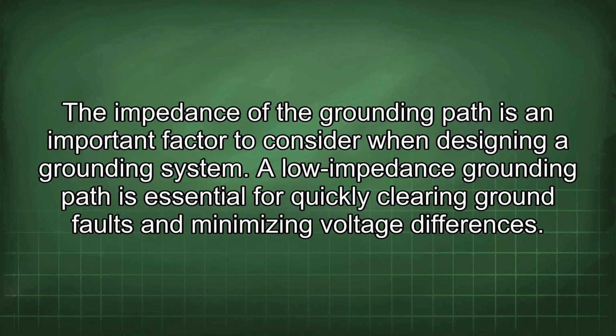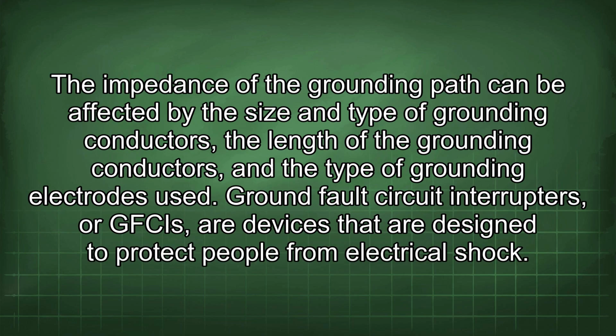The impedance of the grounding path is an important factor to consider when designing a grounding system. A low impedance grounding path is essential for quickly clearing ground faults and minimizing voltage differences. The impedance of the grounding path can be affected by the size and type of grounding conductors, the length of the grounding conductors, and the type of grounding electrodes used.